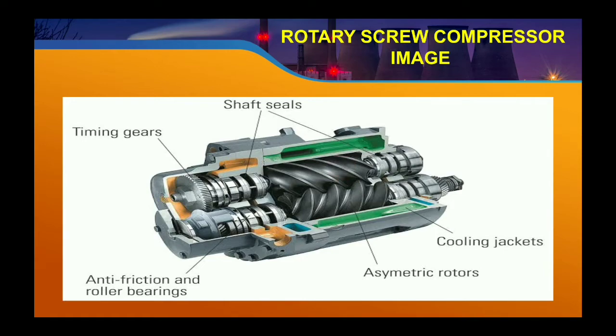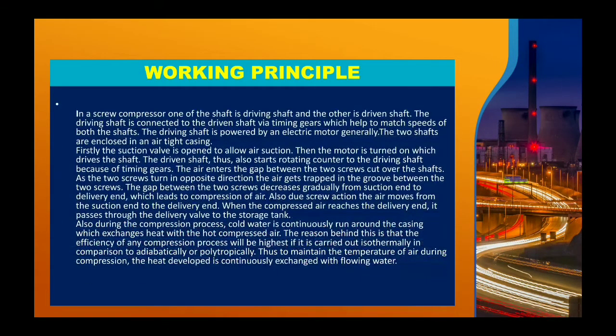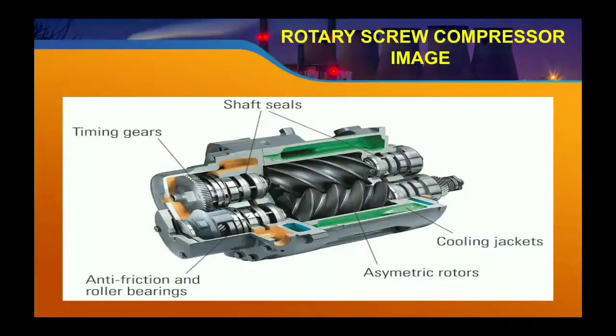Now the working principle of the rotary screw compressor. In a screw compressor, one shaft is the driving shaft and another is the driven shaft. The driving shaft is connected to the driven shaft via timing gears, which helps match the speed of both shafts. The driving shaft is powered by an electric motor. Generally, the two shafts are enclosed in an airtight casing and are in close proximity.